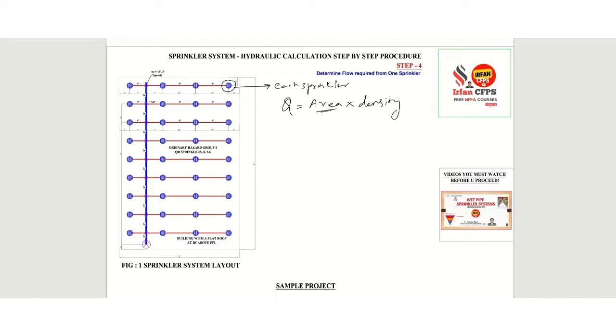We already know the area based on S by L rule, which is about 126 square feet. Density is nothing but the amount of water that falls into each square foot in one minute, and the units will be gallons per minute per square foot.